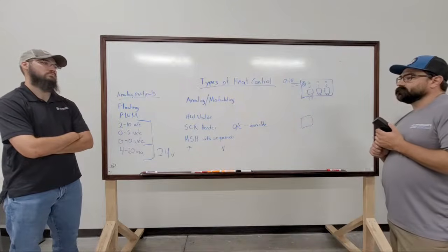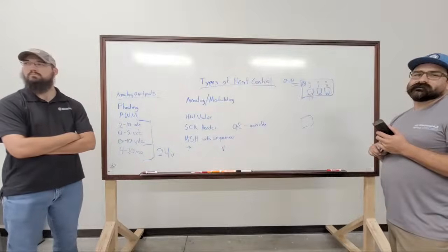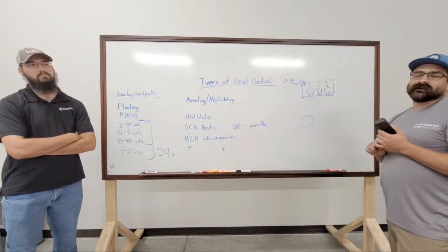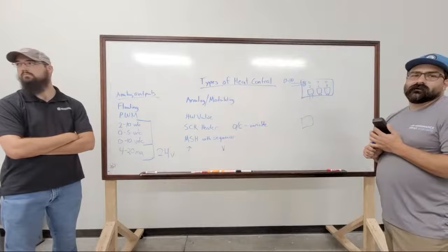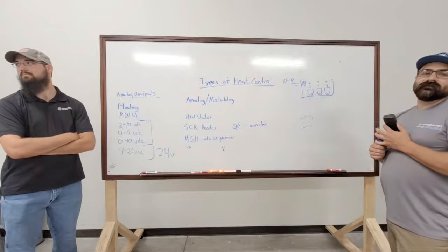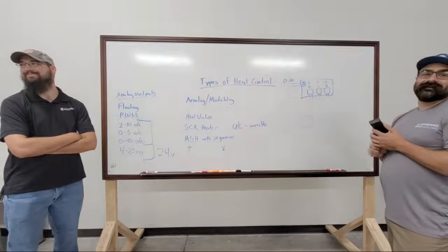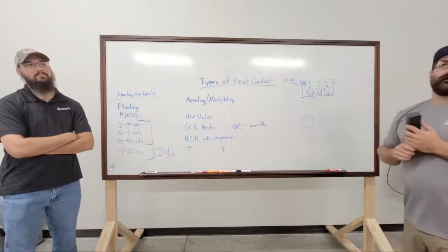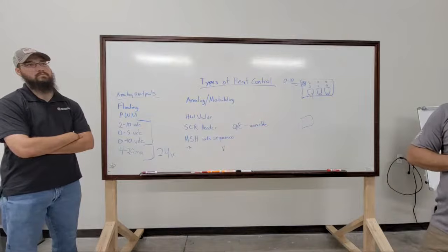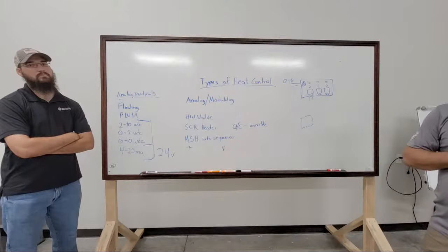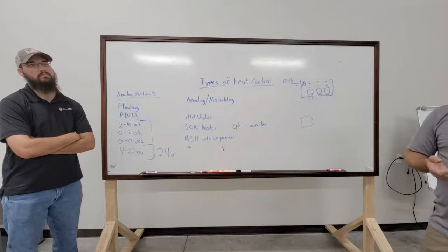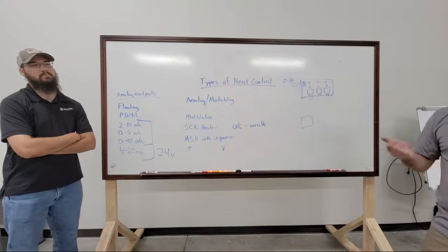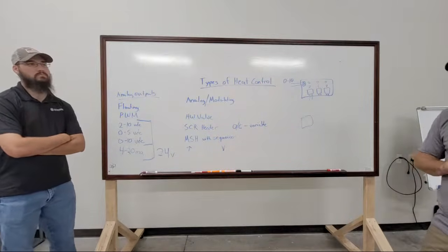I can't remember what those things are called, the little DC pilot relay, huh? Like we get the 10 volt relays. Oh yeah, for the distance. Yeah, we just call them a pilot relay. Well, no, like, we did a job and we used the micro spiders, but we had 3 stages of heat. So on the 3rd stage of heat, because we didn't have outputs on the micro, we had to use an AO to drive a 0 to 10. I guess it was just a pilot relay.